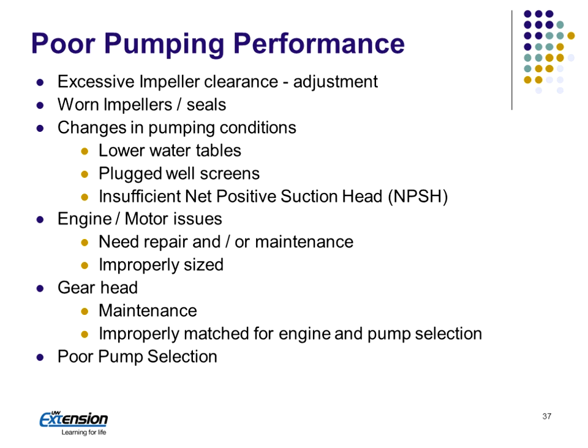Some of the pumping problems we can have: excessive clearance between the impeller and the housing, or worn seals, and we're going to show what that looks like here in a minute. Lower water tables can have an effect, especially on the net positive suction pressure, or plugged screens. Motors or engines either need some repair or maintenance, or sometimes they're improperly sized. An example of that is we may have had a 125 horsepower motor, we changed to a low pressure system, but we didn't change the motor, so now it's running at only 50% of capacity. Larger motors' efficiency drops rapidly when we get below 50%.